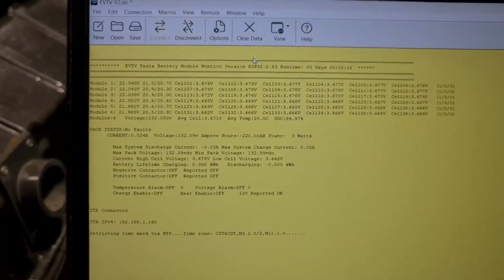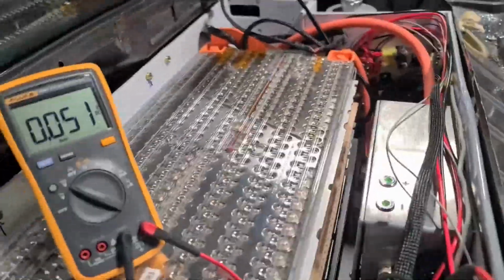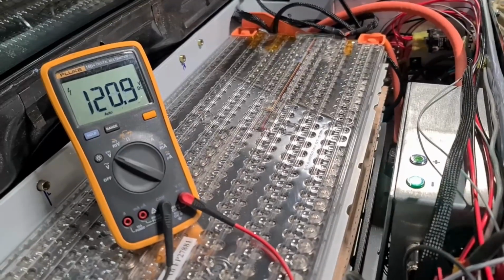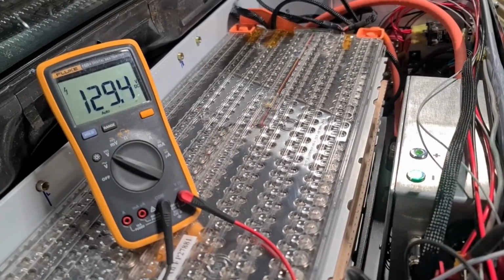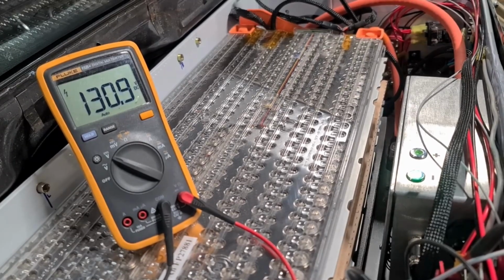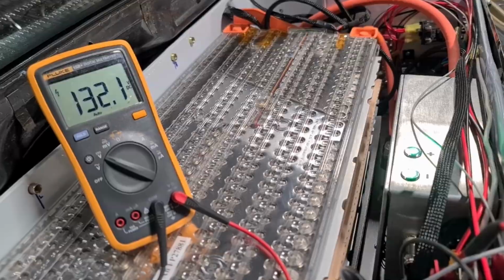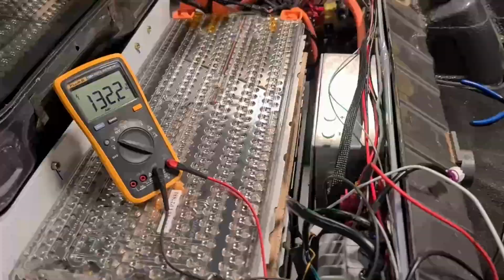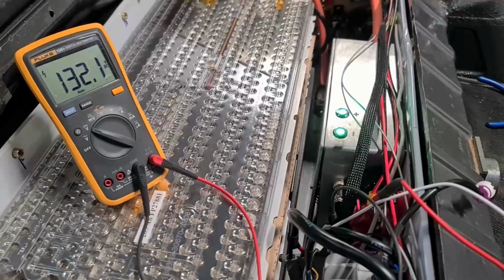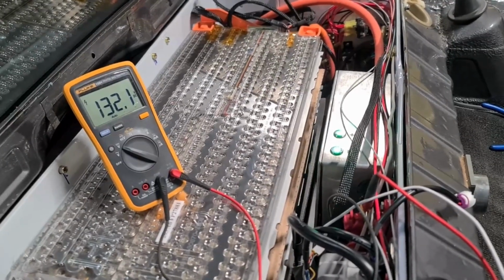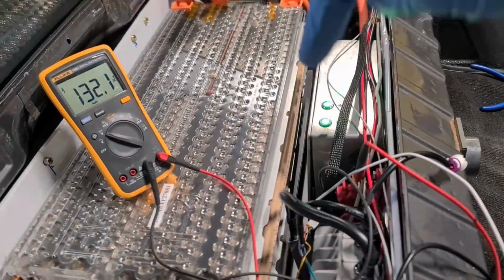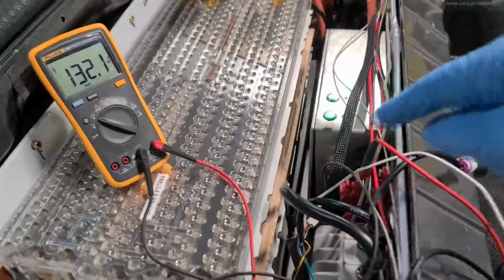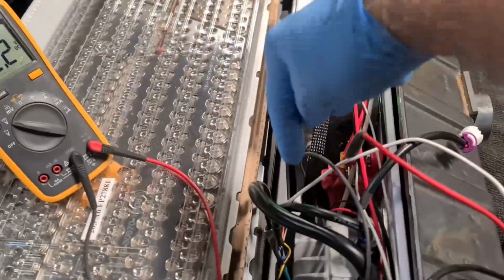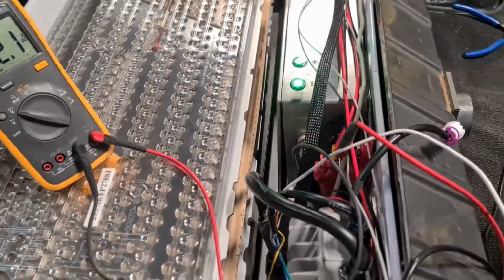Takes a few seconds. Okay, we have 6 modules, we have current, we're getting the timestamp, everything's good. Now let's watch the contactors and the voltage on the pack. There's contactor 1. There we go, 130 volts, and boom! We have full engaged contactors and full power on the output terminals. This is a good milestone, fantastic. Now what I need to do is run the 2 cables down to the motor. They'll both come up through their fittings here and into a right angle terminal.